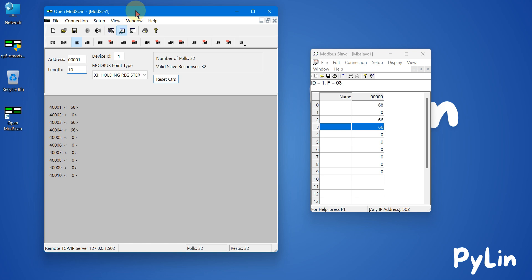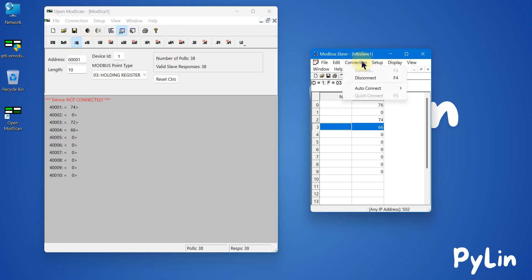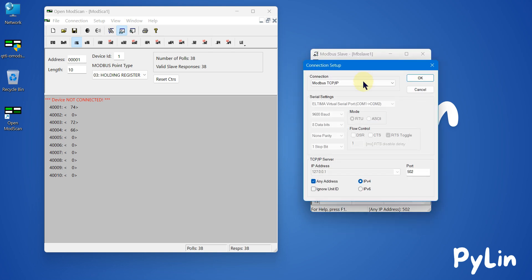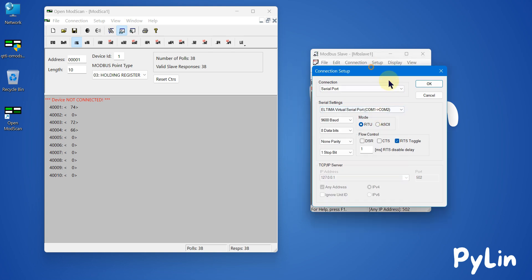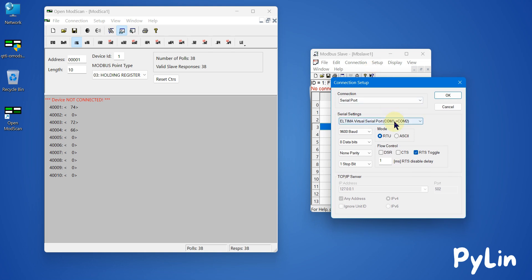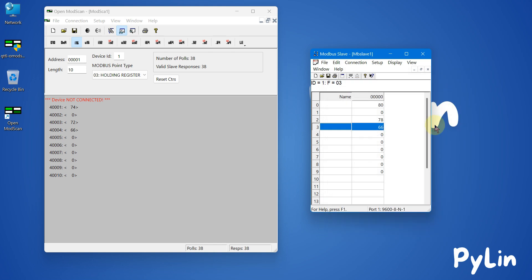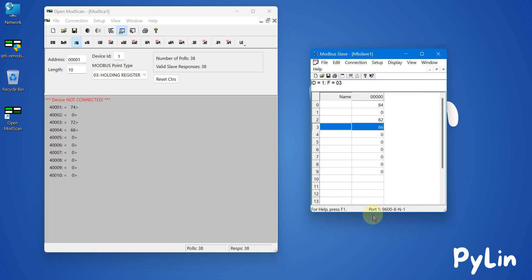This is how you can use OpenModScan to connect with Modbus TCP or Modbus serial devices. Let me also show the serial connection. I'll disconnect from both sides, then in the Modbus slave I'll press Connect and instead of TCP/IP I'll select serial port. I have a virtual serial port running that connects COM1 to COM2. I'll simulate the Modbus serial device on COM1, so the data will be available on COM2. My device is up and running on port 1 with 9600 baud rate, 8 data bits, parity none, and stop bit 1.